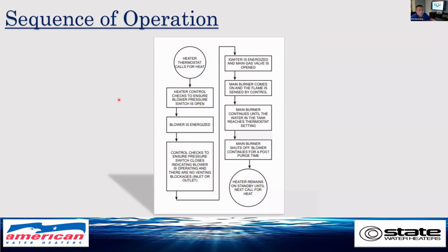Sequence of operation. The most important part of troubleshooting is knowing what steps the unit takes to produce hot water. When you know the sequence of operation, you will not even look at that error code being displayed on that gas valve. I don't ever look at it when I service anything. I cycle that heater and go from there.